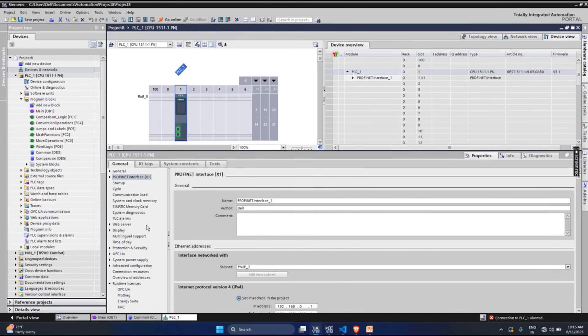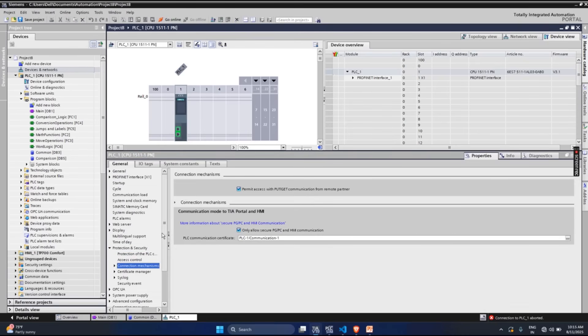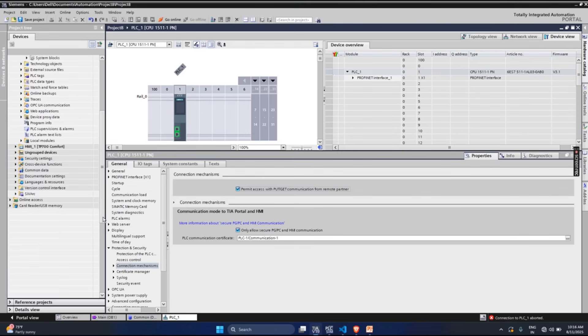Going down to the operating mode, that will be protection and security, then connection mechanisms. Here you need to enable 'permit access with get/put from remote partners'. If this is not enabled, what you need to do is go to security settings.